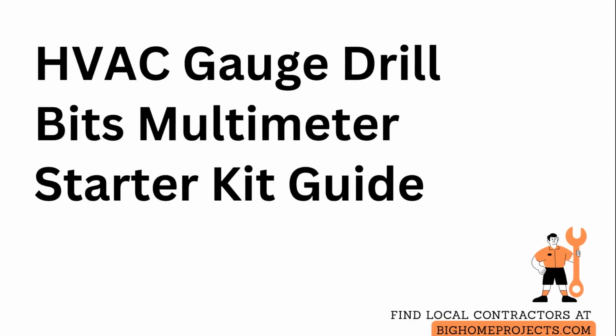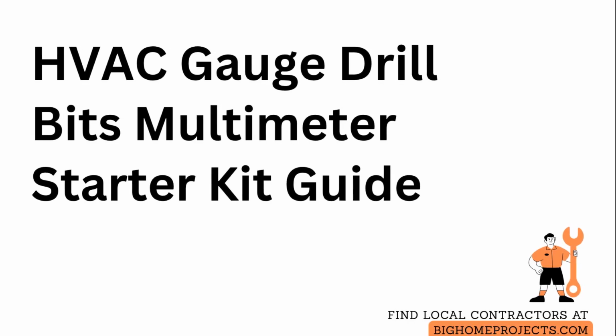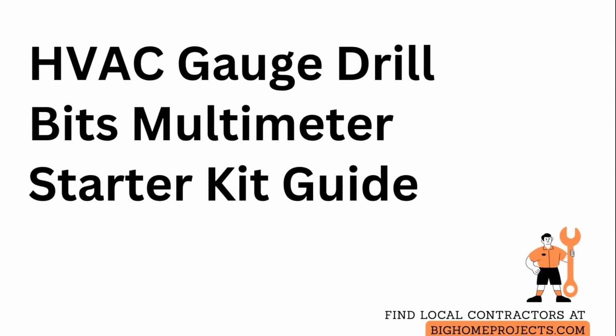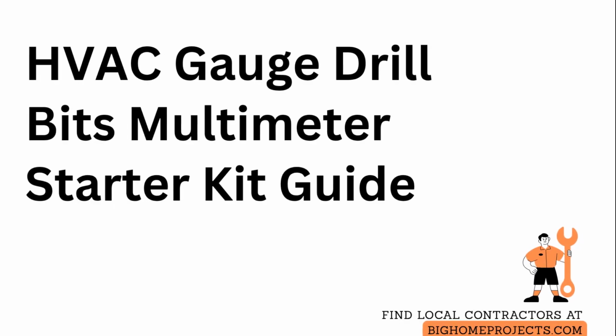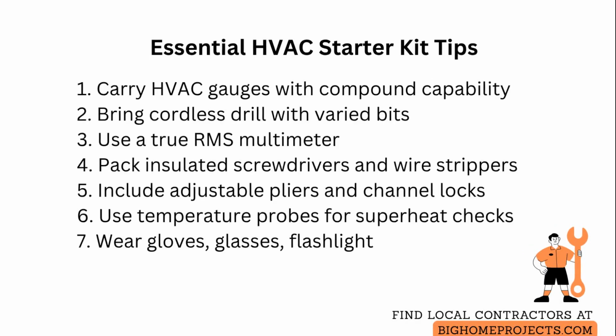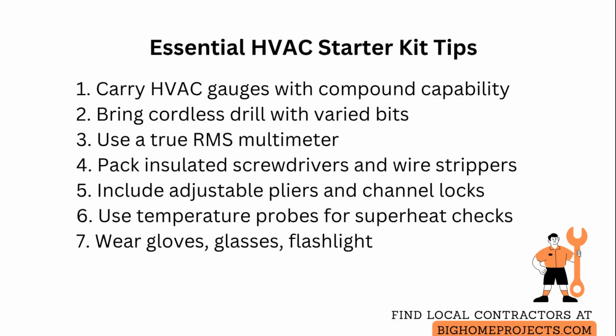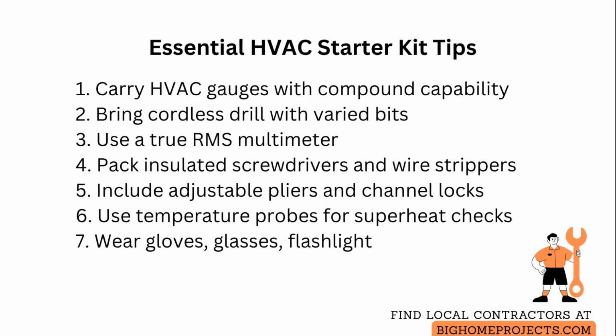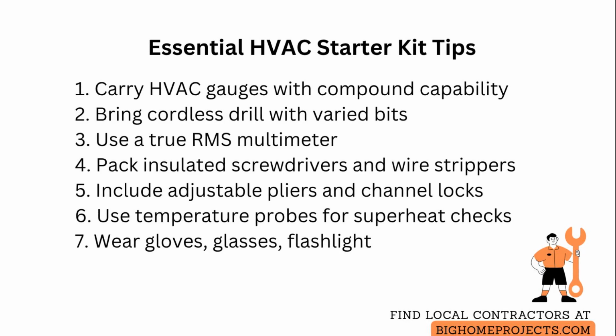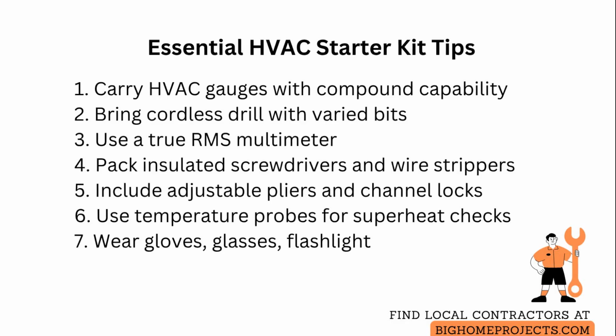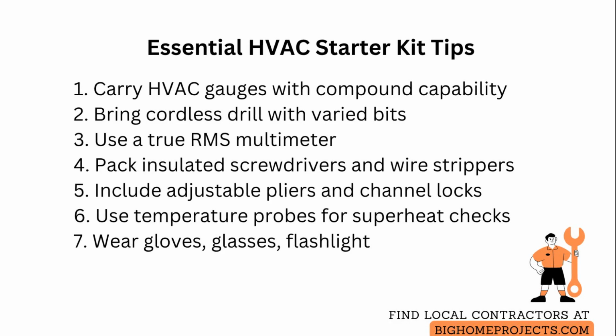For an HVAC service call, a technician needs a compact, reliable starter kit that covers measurement, fastening, safety, and diagnostics. A quality set of heating, ventilation, and air conditioning gauges with manifold hoses lets you read system pressures and perform leak checks accurately, so always carry one with a low side and high side connection and a compound gauge for vacuum work.